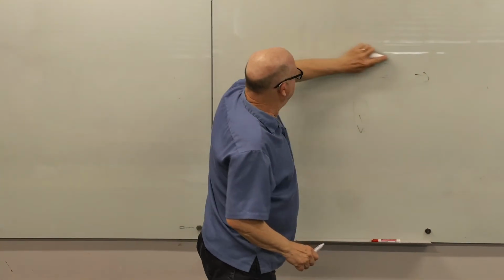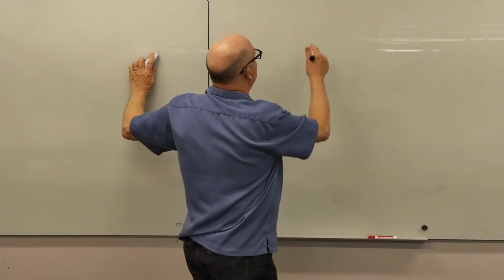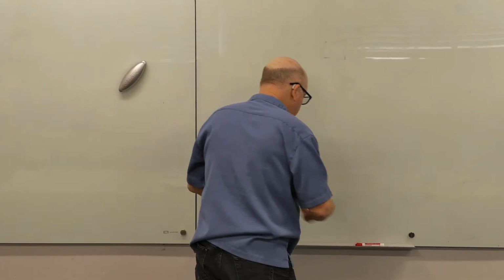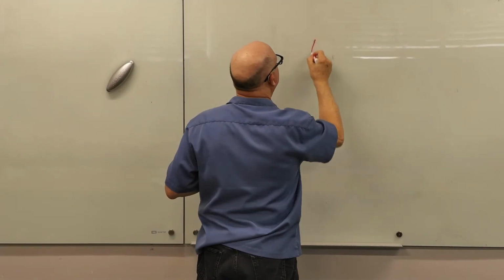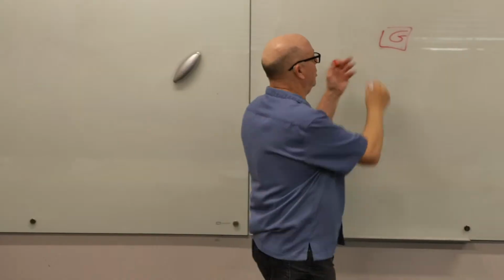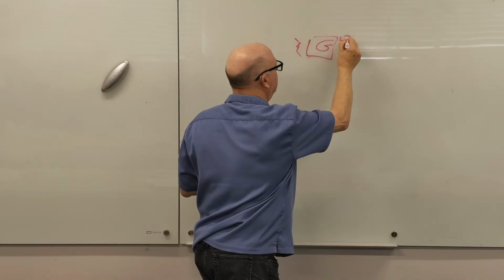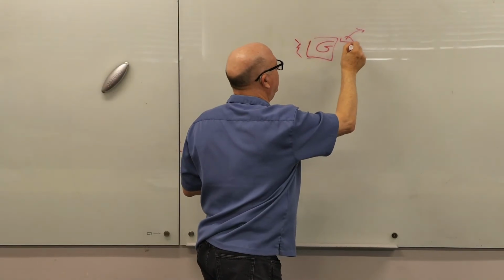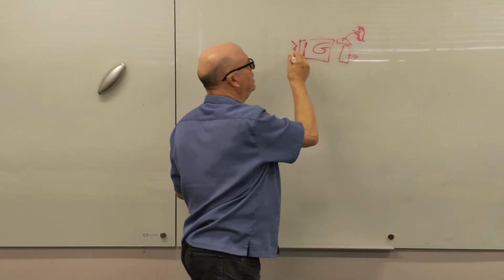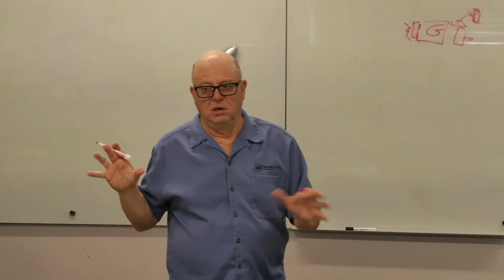So here's a project that we did that will remain nameless. We had an air handling unit serving a surgery center. And this air handling unit had a real big beefy fan in it because it not only had pre-filters, but then it was blow through. There's a cooling coil, there's a hot coil. We had a hot deck, we had a cold deck. We had super duper secondary filters built in. I mean, this was a big motor, big air handler.